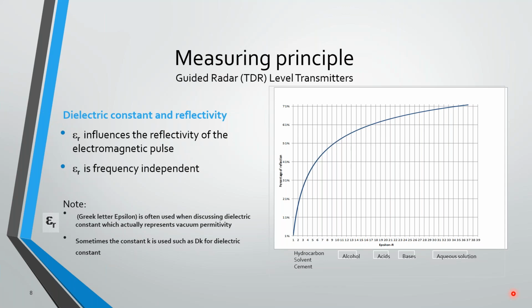One of the big things with radar level devices, whether guided wave or non-contact, is the dielectric constant of the material we're trying to measure. Dielectric constant determines how much reflectivity we get from that material. Epsilon R is used as an abbreviation for dielectric constant, though sometimes you'll see just the lowercase k or dk, depending on which manufacturer's literature you're reading - they use different abbreviations.